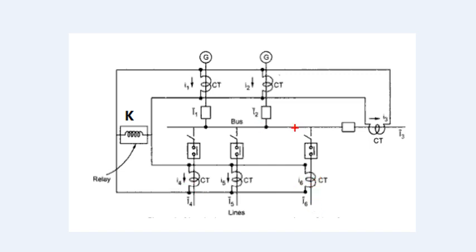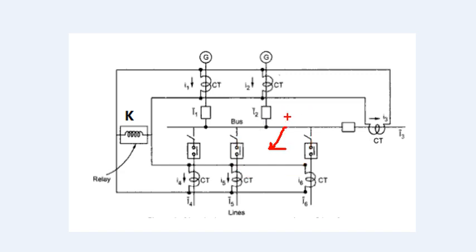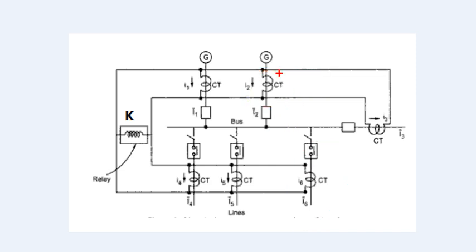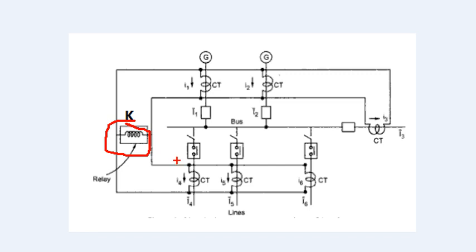If there is a fault inside the bus bar zone, the current becomes unbalanced. The CTs will read different values because extra fault current flows. This causes a differential current, and the relay will operate. This is the basic bus bar differential protection scheme.